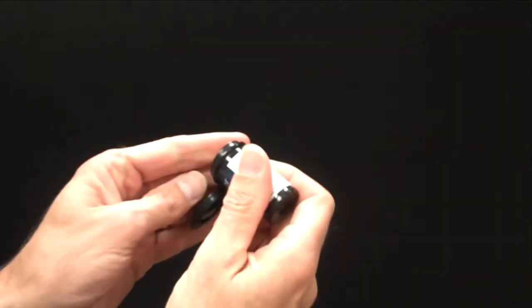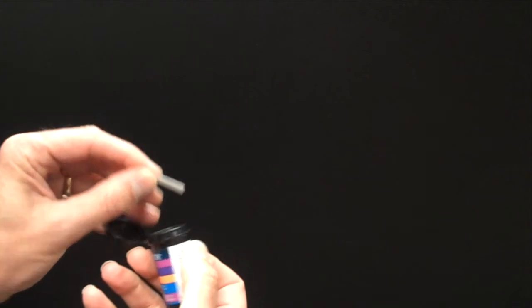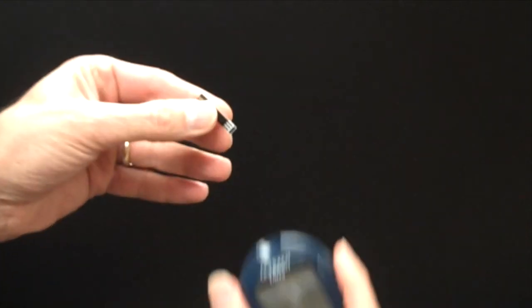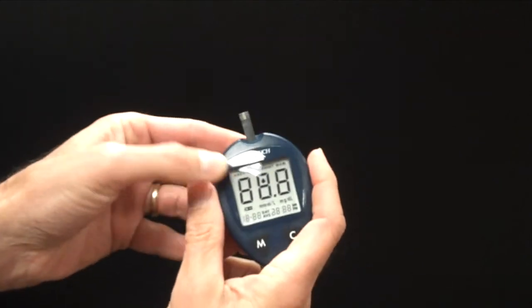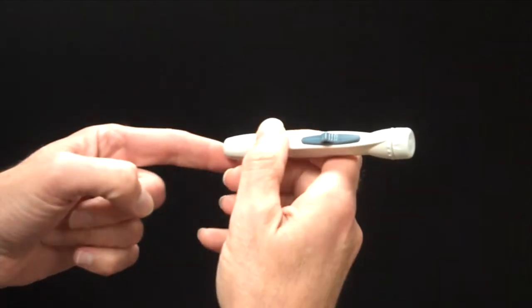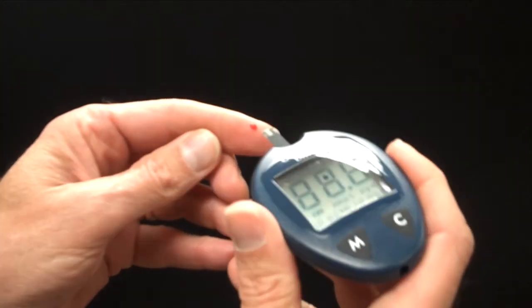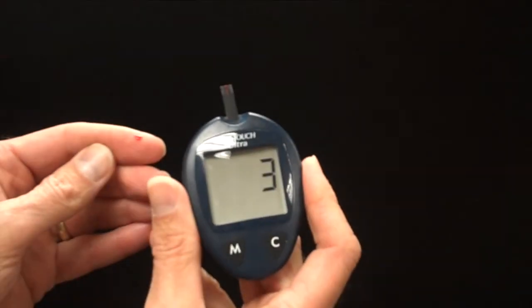This device uses disposable test strips that are inserted into the meter. The user applies a sterile lance to draw some blood. The tip of the test strip draws up some sample by capillary action.